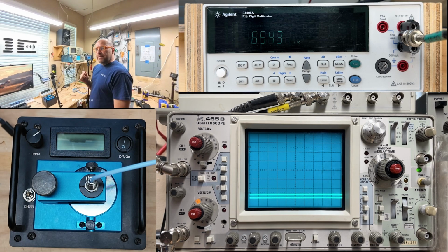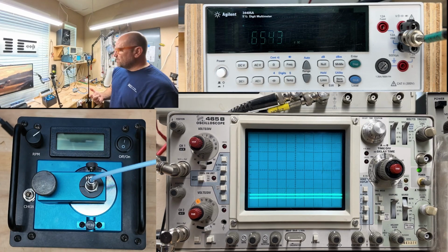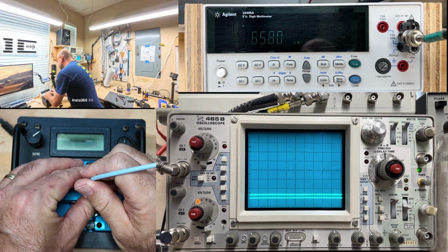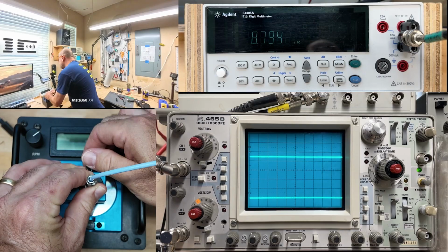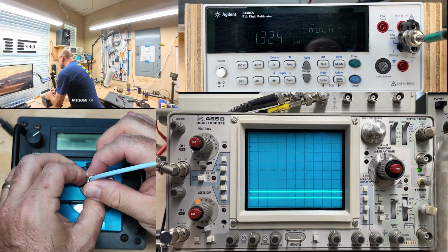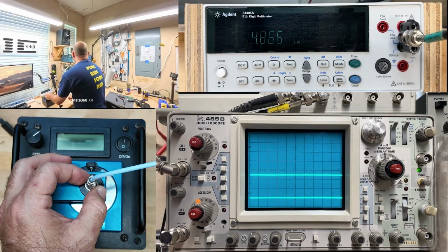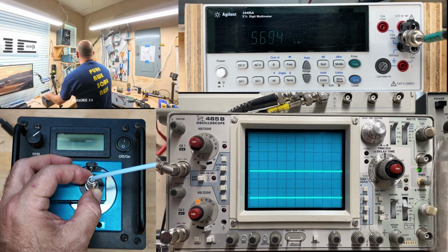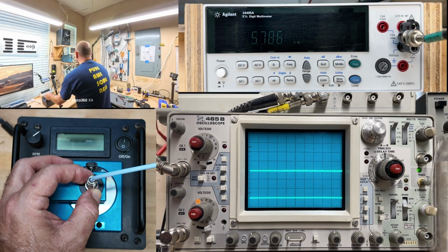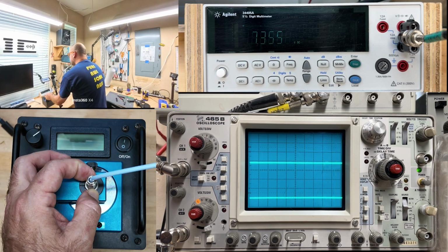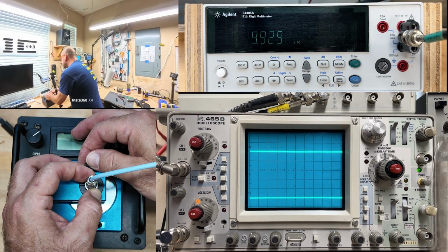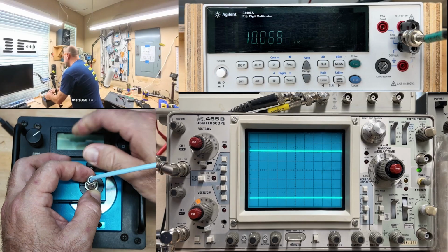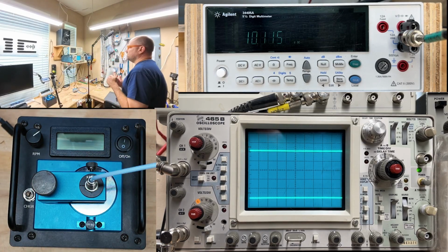Now in reality, we don't set probes to touch against the shaft. We back it up, and we usually use a gap voltage of 10 volts. That is at the middle of the working range of the probe. So I'm going to back my probe out till we have 10 volts. The cool thing is as I move it out, it's also moving on the oscilloscope because we're measuring the voltage. At 3 divisions, we're basically at 6 volts. We're going to keep going up till we get to 10. We are there. We are basically at 10 volts.